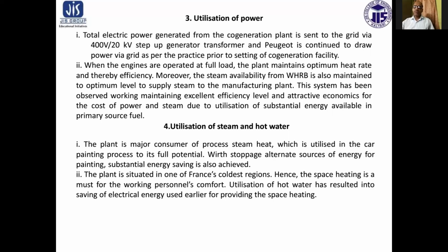Utilization of power: the total electric power generated from the cogeneration plant is sent to the grid via a 400 volt by 20 kilovolt step-up generator transformer, and Peugeot continues to draw power via the grid as per practice prior to setting up of the cogeneration facility.